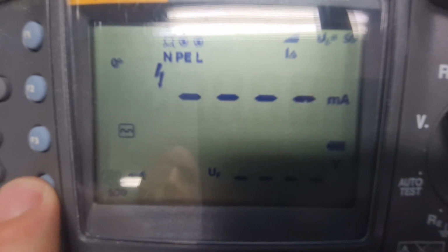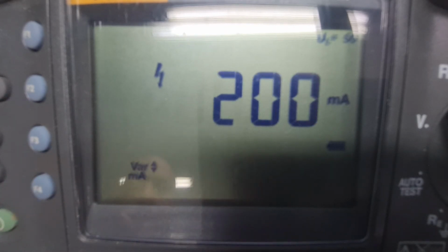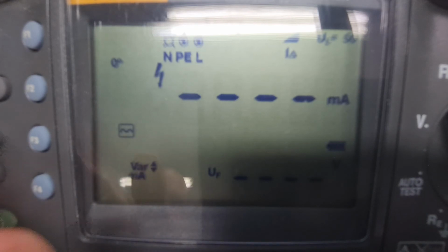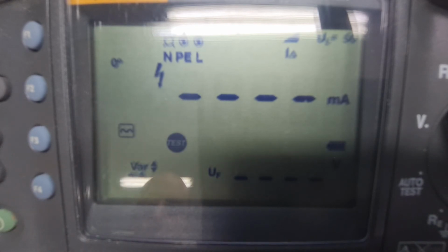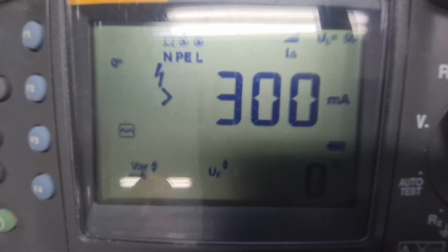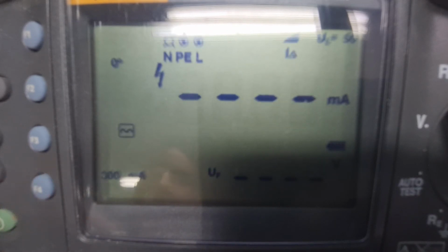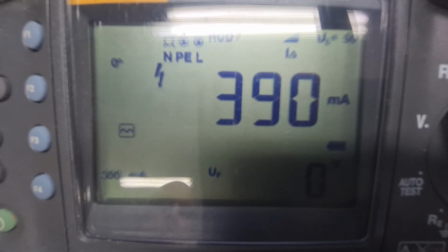Now I am going to set the instrument to a variable leakage current. I am going to go to 200 milliamps. I press test, wait for some moments, and once again I do not get any trip. Let us try with the 300 milliamp setting. And now we finally get a trip for the DC ripple current at 390 milliamps, which is exceedingly high, and this provides no protection to the final circuits.